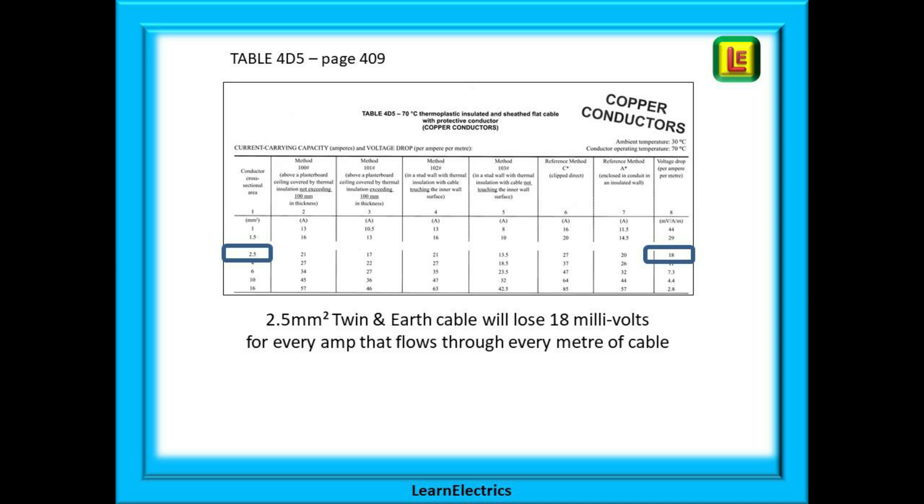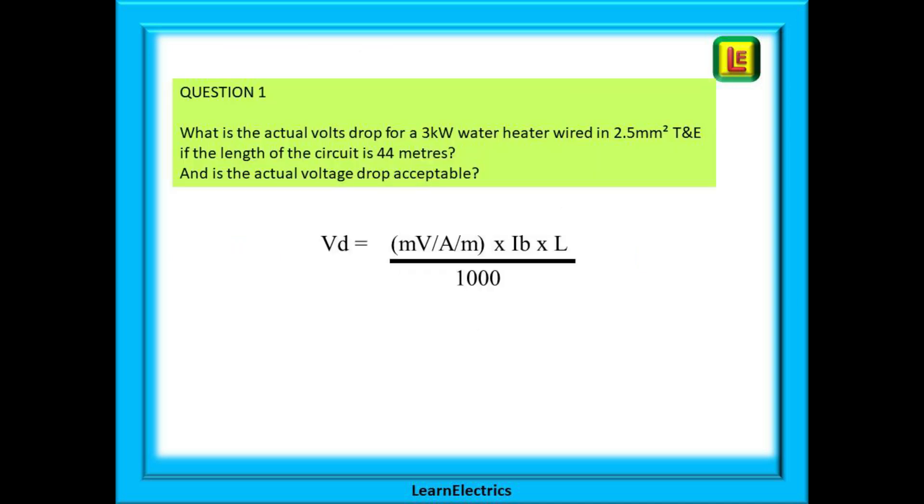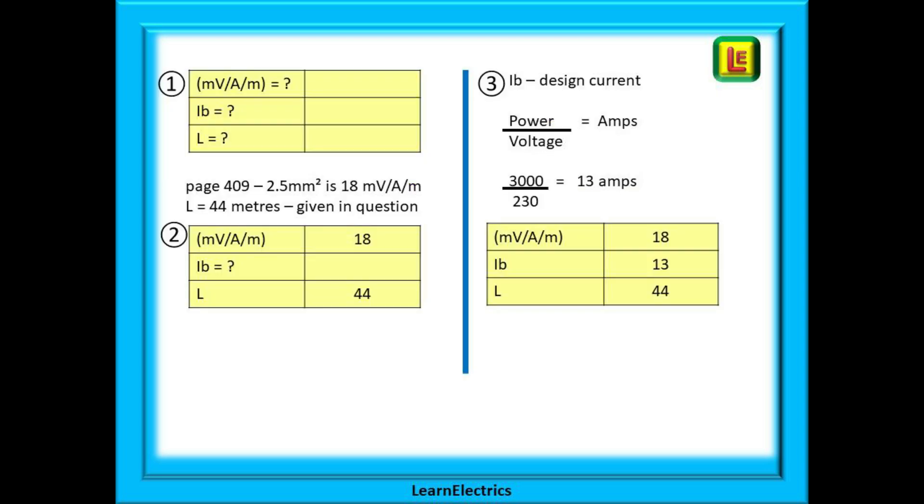Let us now work through a typical exam question and see the calculation in action. The question is: what is the actual volts drop for a three kilowatt water heater wired in 2.5 millimeter twin and earth cable if the length of the circuit is 44 meters, and is the actual voltage drop acceptable? What do we need to know? The box at number one shows us that we need the mV/A/m number, the design current or Ib (in other words, what the water heater is designed to consume when it is turned on), and we need to know the length. We can enter some data into the box at number two just from reading the question. In the third section we will calculate Ib from the power and voltage.